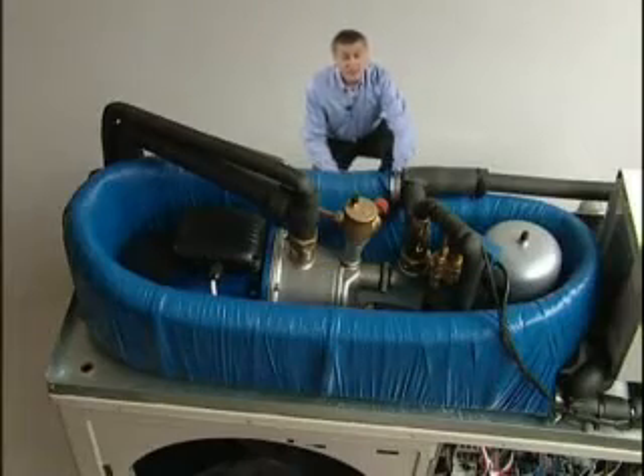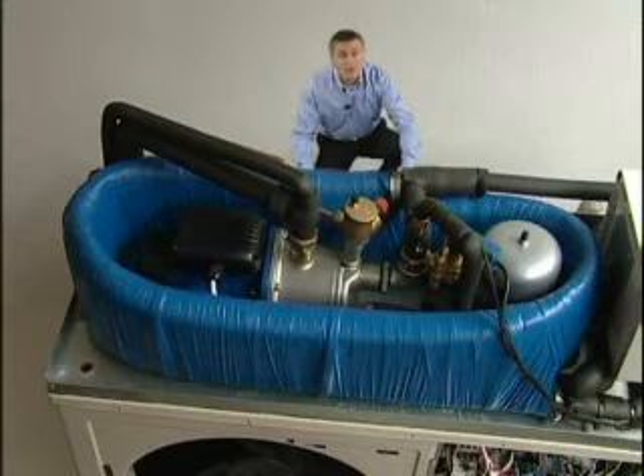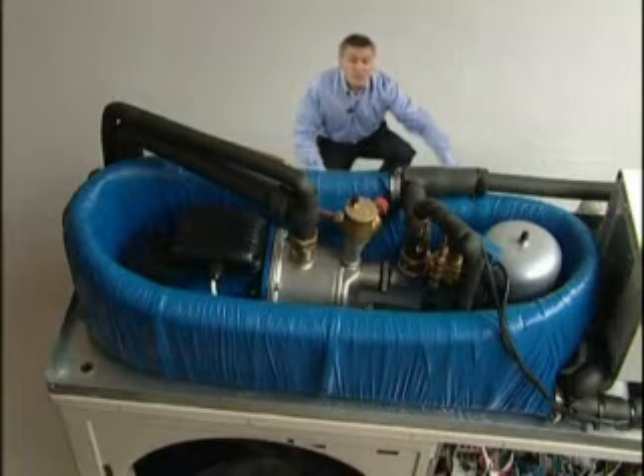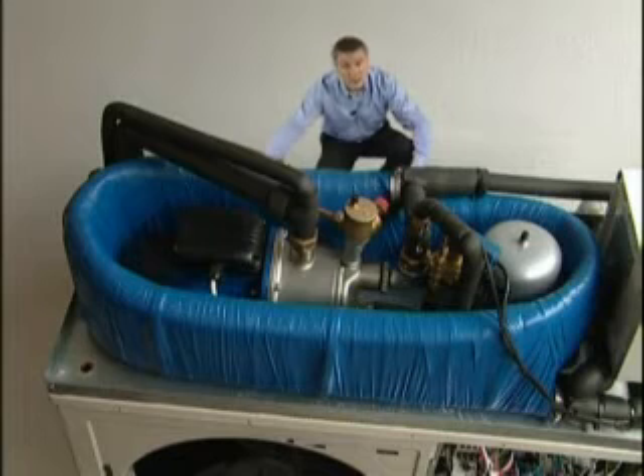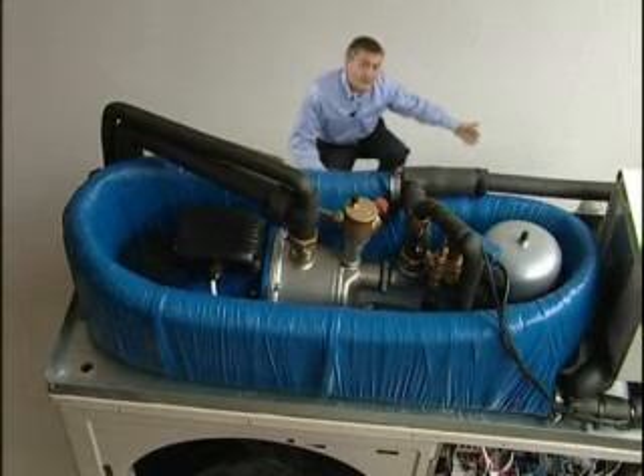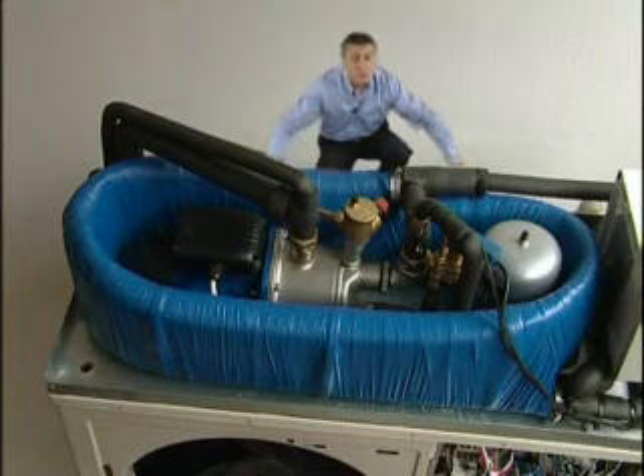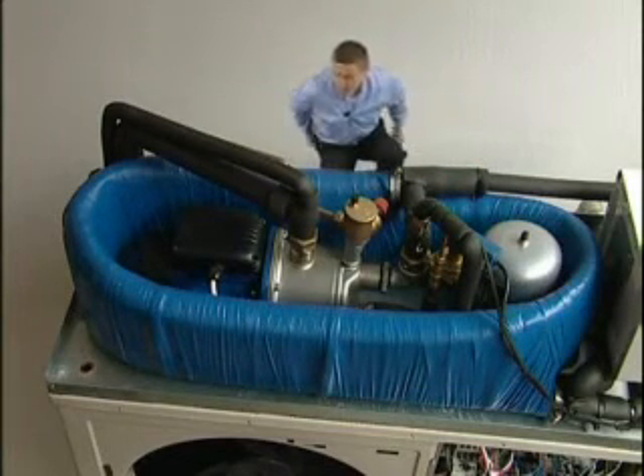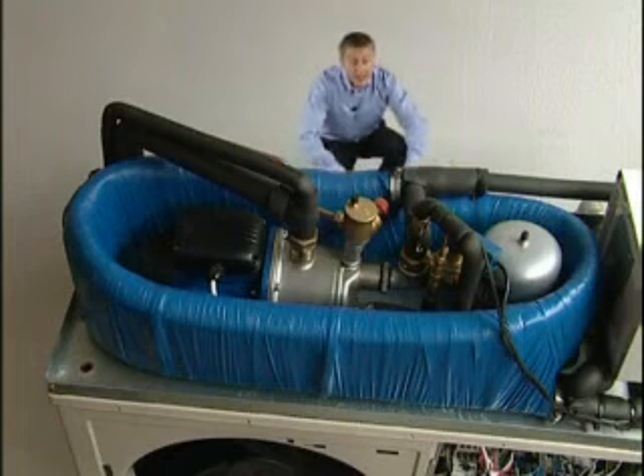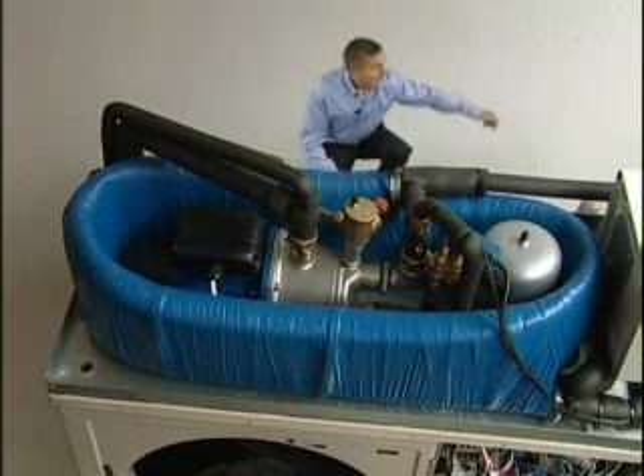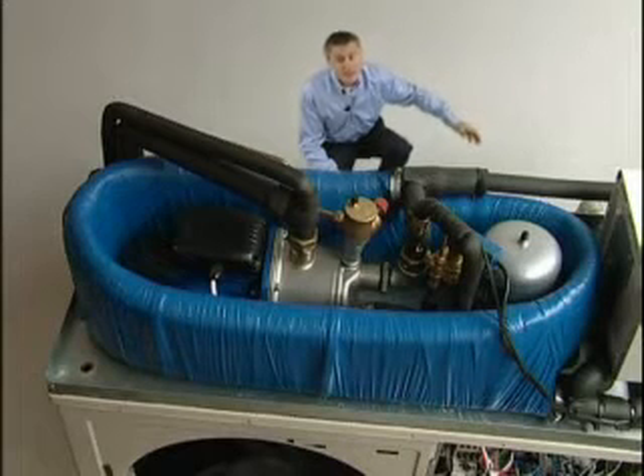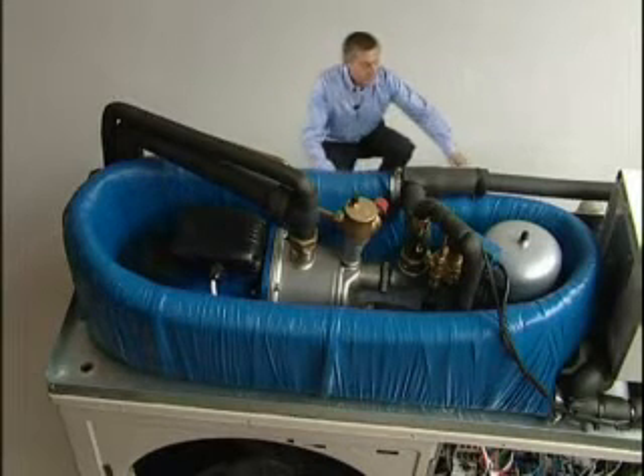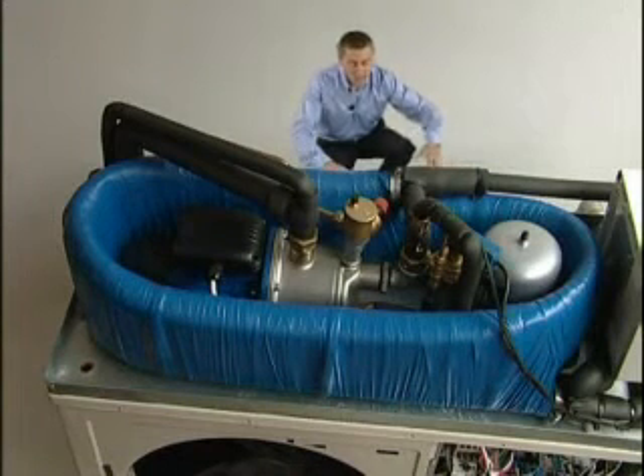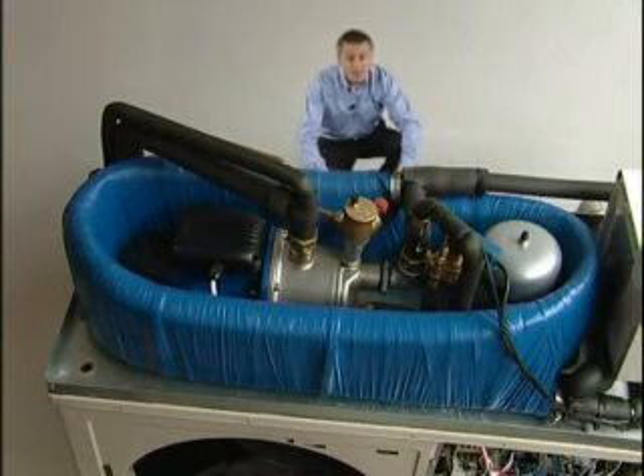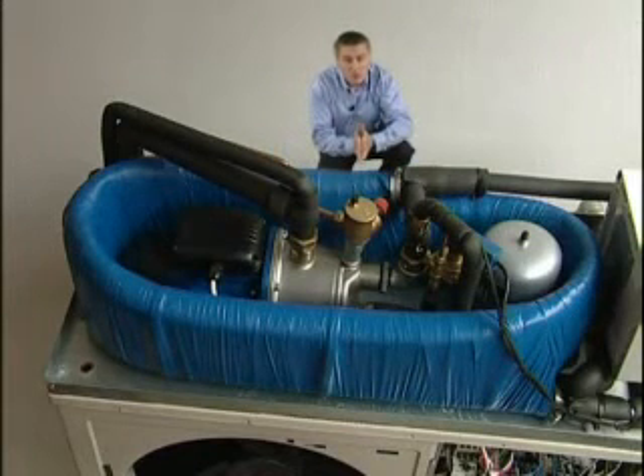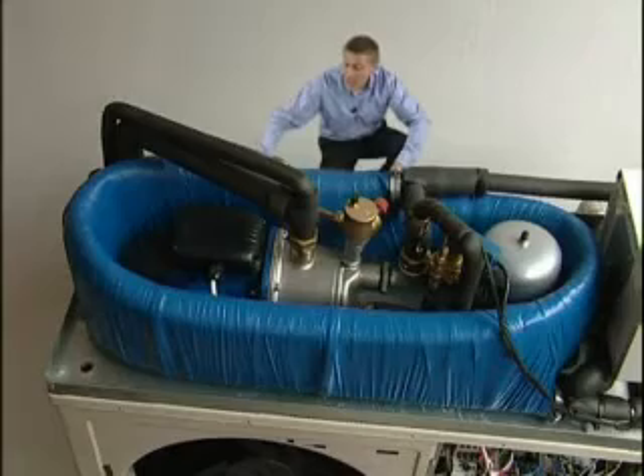Now we can look at exactly what happens inside the machine itself, at the entrance of the water from the piping, at the exit of the water from the piping, and in particular at the entrance of the gas that arrives through the piping in the exchanger, which we can see at the moment. The gas, which has been heated or cooled by the external condenser, enters the heat exchanger. The water enters, and according to the temperature change required at the exchanger, it comes into contact with the refrigerant.